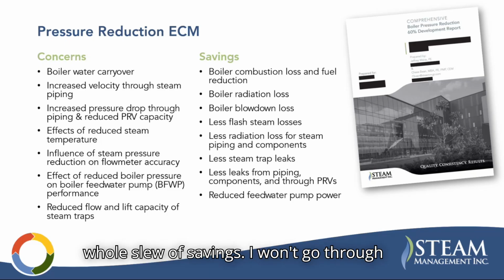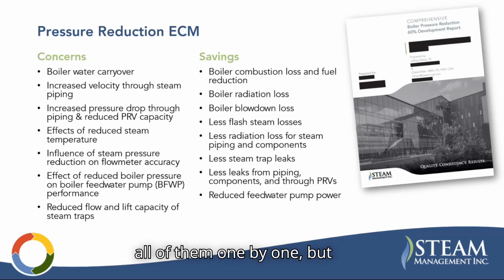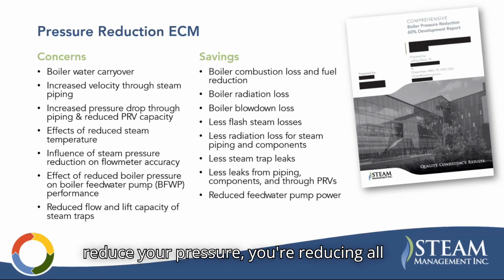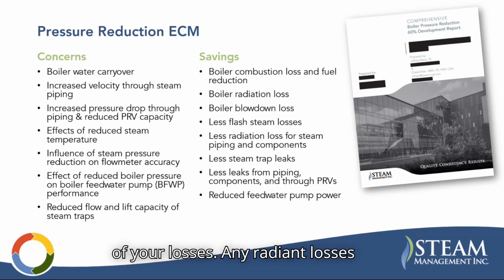But there's a whole slew of savings. I won't go through all of them one by one, but generally speaking, if you reduce your pressure, you're reducing all of your losses. Any radiant losses through your distribution system, any leaks are now leaking less. Failed steam traps are now leaking less.